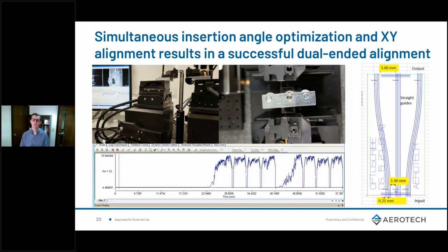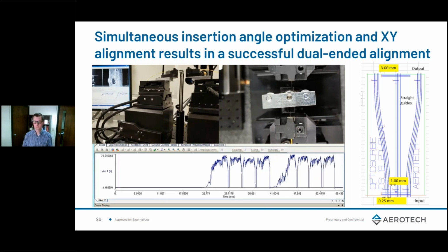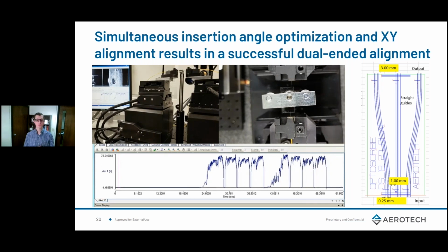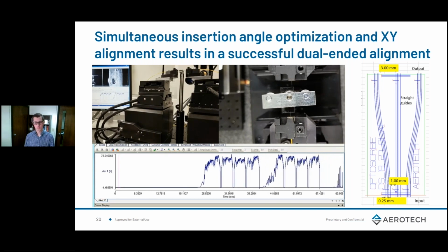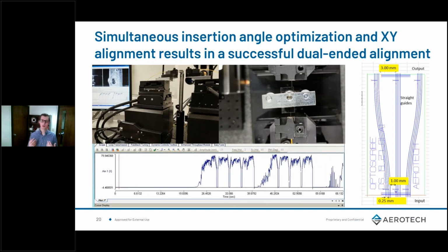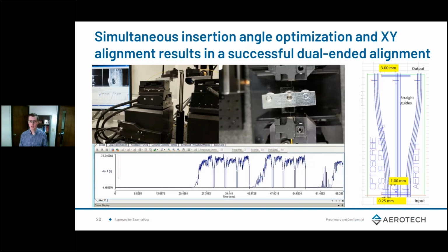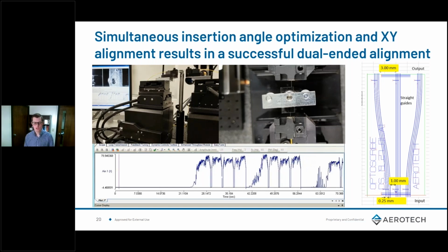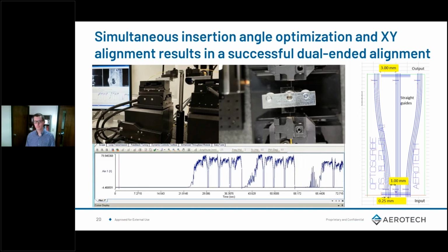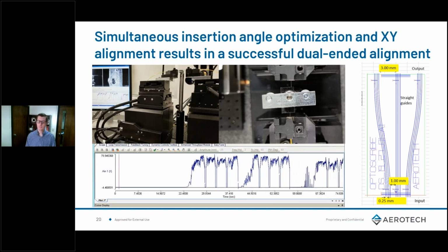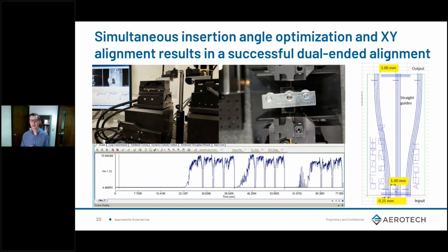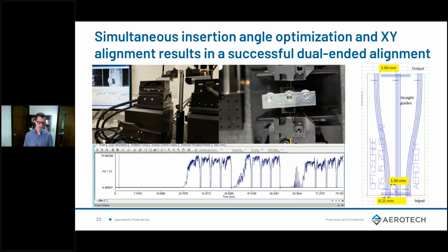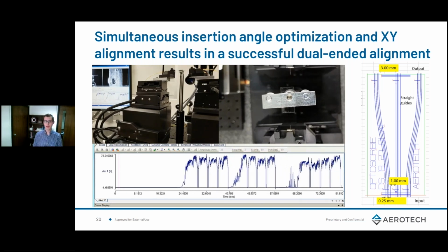And here you'll see it's going to make the longest move, the full length of the substrate. And as I mentioned, this is not calibrated, so we expect a larger error at our tool point or at our tip of our fiber, as we mentioned. And you'll see that strange shape in the power plot at the bottom of the screen. That's because we actually couldn't find the optical profile initially and had to search for it due to that accuracy. So if these stages were calibrated, we would have found the optical profile immediately.